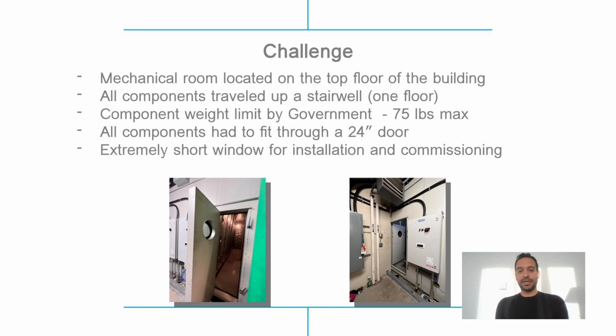The challenge for them, firstly, it's a remote location. It's a challenge to do anything in that part of the world. But also they had a problem with space, and they had a problem with weight. The AHUs were located in the mechanical room that was on the top floor. The elevator would go to the top floor, but they still had a flight of stairs to take everything up to the mechanical room. So not only they had to fit everything in the building, fit everything in the elevator, they also had to take everything up to the AHUs and install everything.